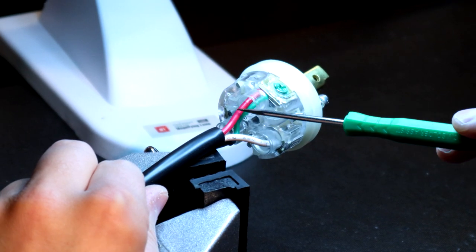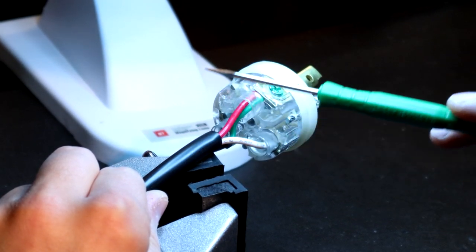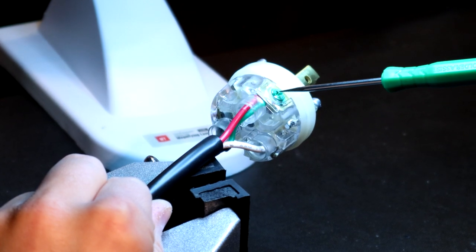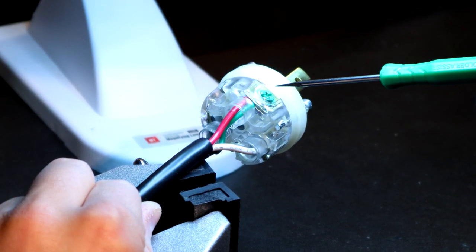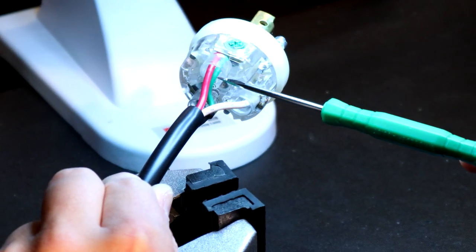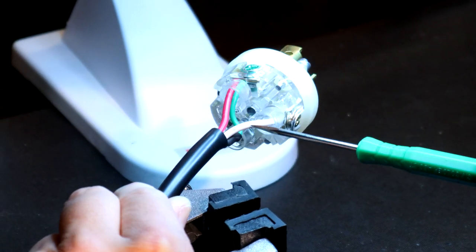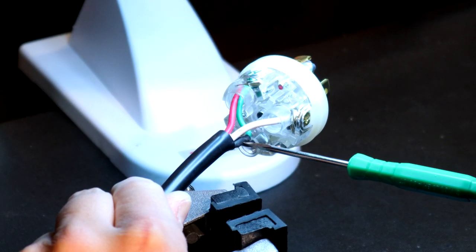You can see here on this particular cable the red lead is the ground. The red lead is an arbitrary color as far as what lead we actually decide to use for ground. However, you can see how I identified it on the opposite. This is inside the connector. You can see the ground terminal right here. It is the one with the green on it.